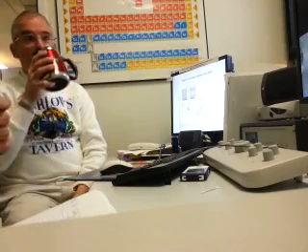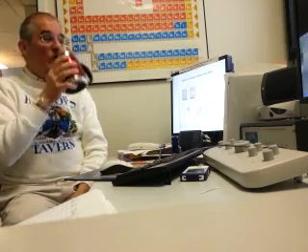So they're accelerated into the detector where they're converted from electrons to photons, and then the photons go into a photon amplifier or multiplier, and that then gets sent off to your view screen. What's the difference between the collection in the secondary electron detector compared to the X-ray detector? Speed of the electrons hitting it.